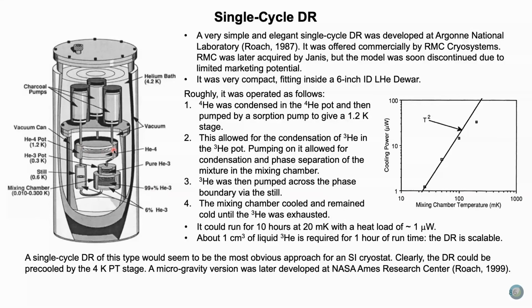So, how this operates roughly is the helium-4 is condensed into the helium-4 pot. This is the helium-4 pot. And then it's pumped on by a sorption pump right here. I'm not sure which one it is, but one of these is the sorption pump that goes with the helium-4 pot. And as that pumps it, it gets down to about 1 Kelvin. That's cold enough to allow for a condensation of helium-3 in the helium-3 pot, which is here. Condenser, which is in very close thermal contact with the mixing chamber.